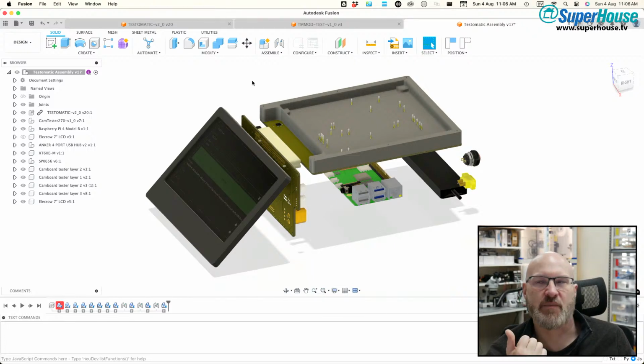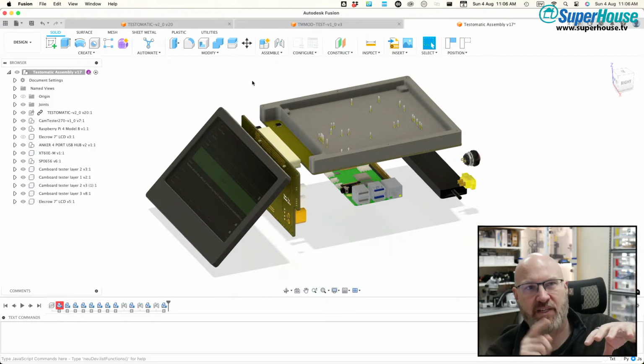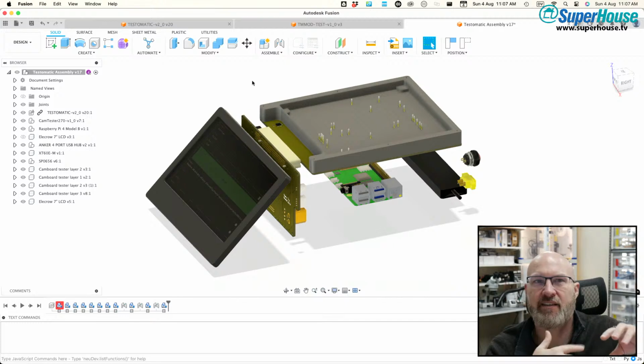You don't need to load firmware on it, you just want to be able to initialize it, take a reading from it, verify that the reading makes sense, and you're done. That process from the time the test starts to the time it finishes might be half a second. So you mount the module, press go, and half a second later the test is done. It knows if it's communicated, if it's been able to initialize the device or not.